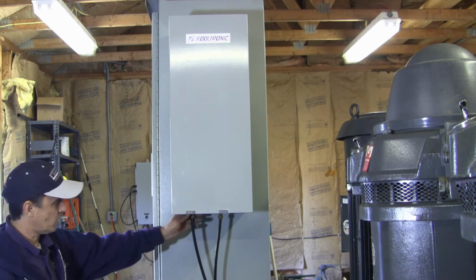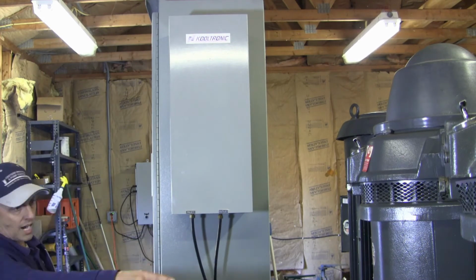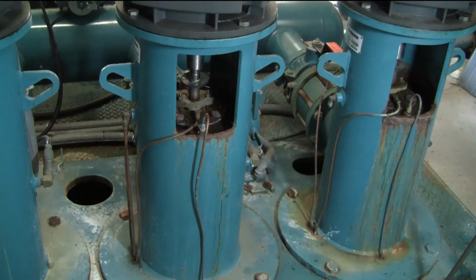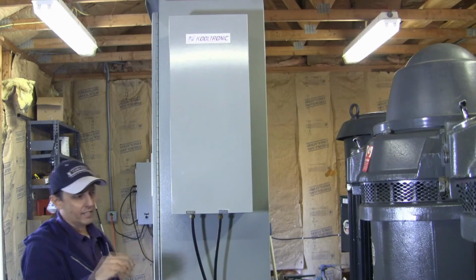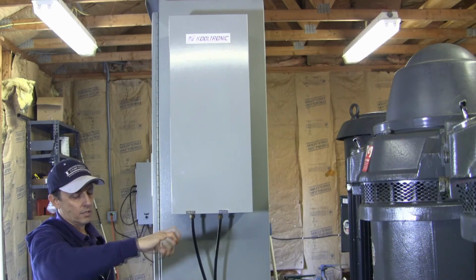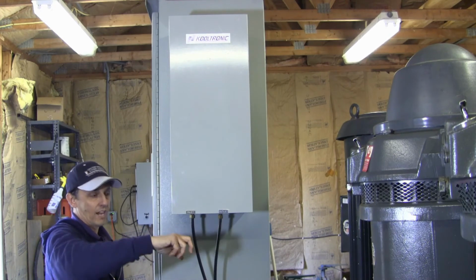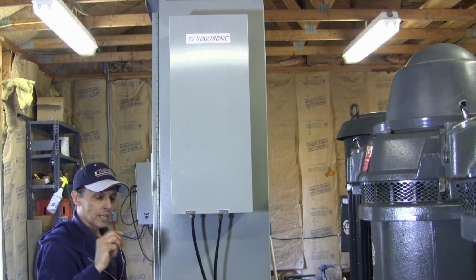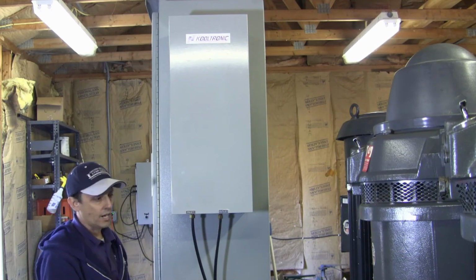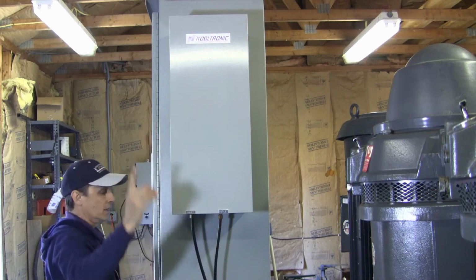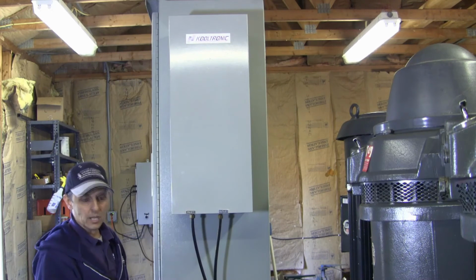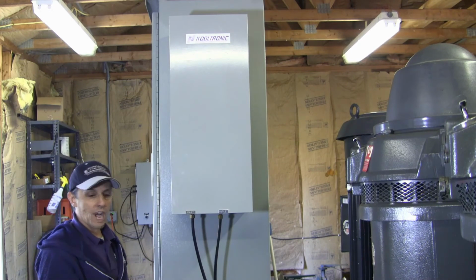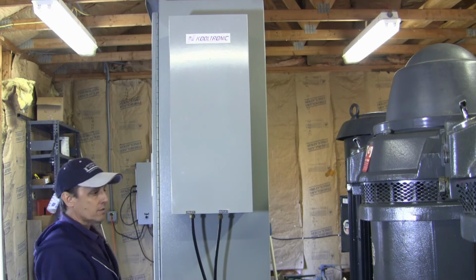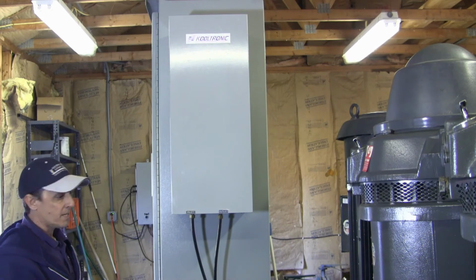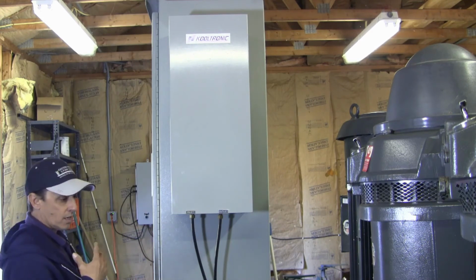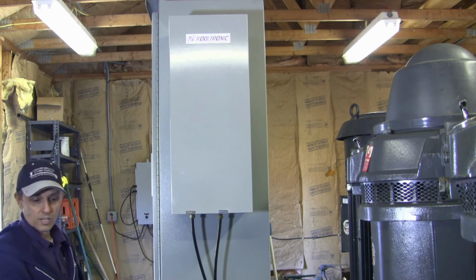That'll be one of the most frequent things. It's either something's clogged in one of the tubes, a lot of times where it goes into the discharge pipe. A lot of people will regulate the amount of water through that. There's a ball valve, or a gate valve actually, and they'll regulate the amount of water going through there. And it's a smaller opening, and sometimes dirt will get in there and clog it up, and then all of a sudden you have no circulation at all. The fan will be running, no water circulation, the panel will heat up. There's a safety on the drive where if it gets too hot, it will shut everything down. So that's one of the things we check out every time we do our PMs. Make sure you got good circulation through your heat exchanger, and make sure that's working okay and everything is cool inside the panel.